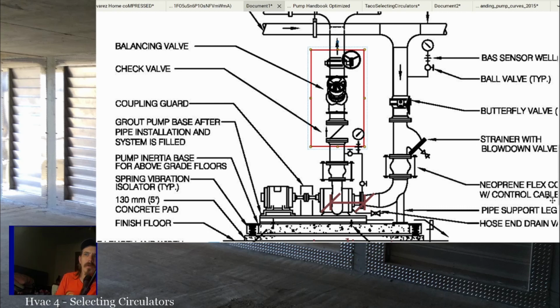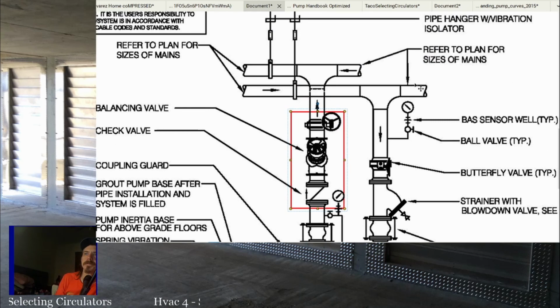You never balance a valve on the suction side, right? Because if you balance it on the suction side, it's going to cavitate. If you balance it on the discharge side, it's no big deal. We're just basically increasing the head that pump needs to work against to get the amount of flow that we want, which is why we generally select pumps that have higher flow rates and can handle higher head than we actually need, because we can always balance that pump down. We can't balance it up, right? Unless you have a VFD, you're not going to be able to get any more performance out of that pump than the performance curve. And even if you do, it's probably not going to be good for it. So we always balance down after the pump. And the check valve after the pump is just generally a good idea in most cases. And then you go from there.